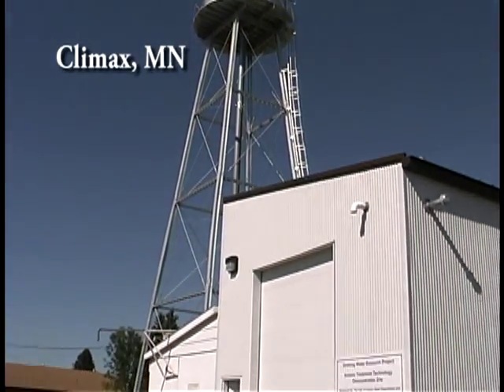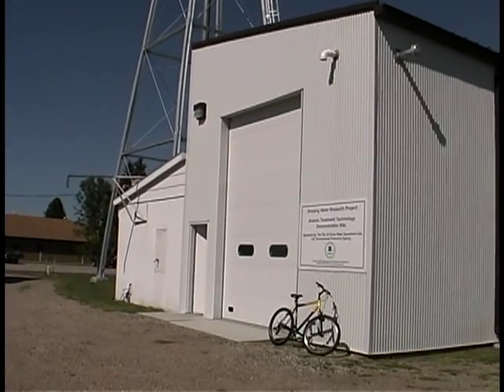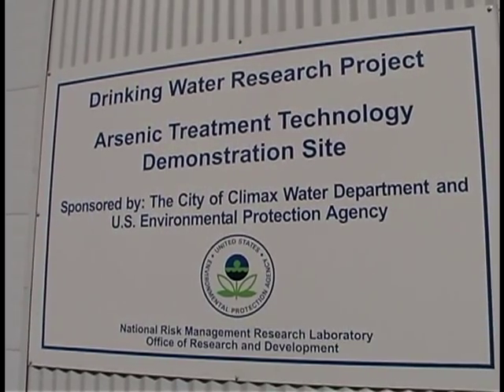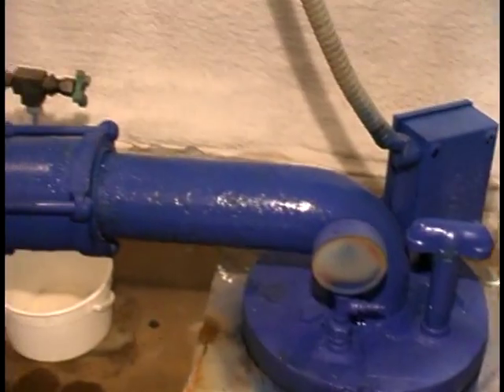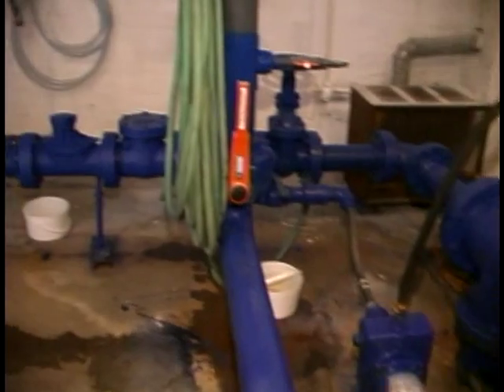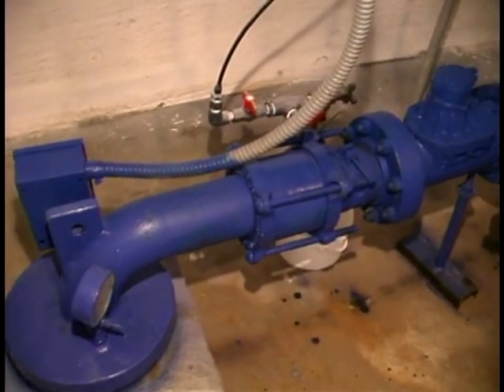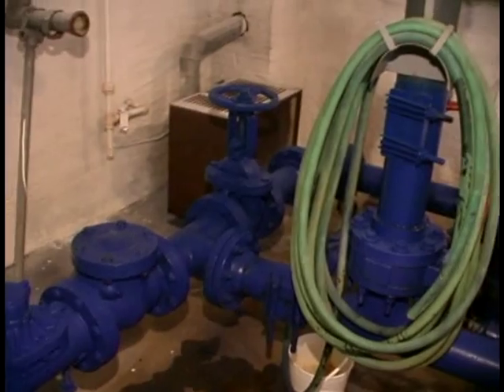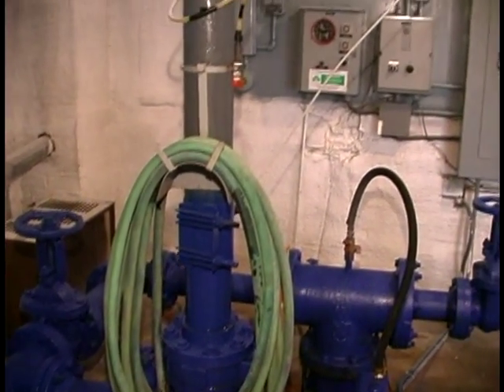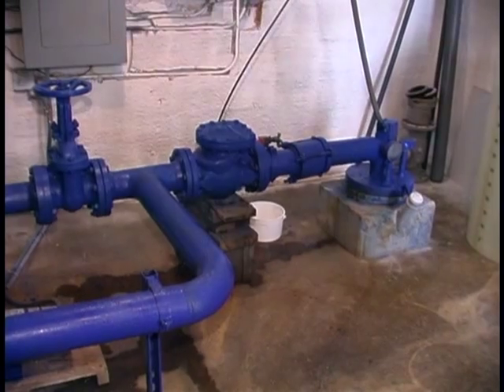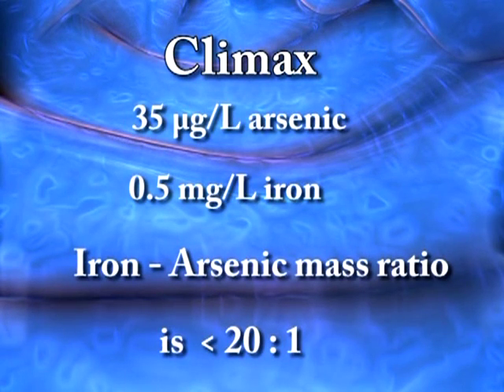Climax, Minnesota is also using coagulation filtration to remove arsenic and is participating in the EPA Arsenic Demonstration Project Round 1. Climax has two 140-foot deep wells with flow capacities of 140 and 160 gallons per minute, though only one well is operated at a time, alternating monthly. The wells have about 35 micrograms per liter of arsenic — primarily arsenic 3 — and 0.5 milligrams per liter iron, representing an iron-to-arsenic ratio of less than 20 to 1, which is below the ratio needed for efficient arsenic removal.